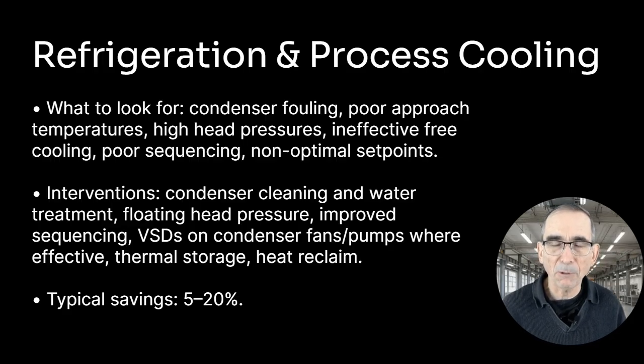So the interventions can just be the boring stuff like improved condenser cleaning, maybe looking at some inbuilt cleaning systems, effective water treatment for these cooling towers, having floating pressures depending on ambient conditions or load, improved sequencing, variable speed drives, thermal storage, heat reclaim. Again, it's quite complex, but typical savings could be 5 to 20%.